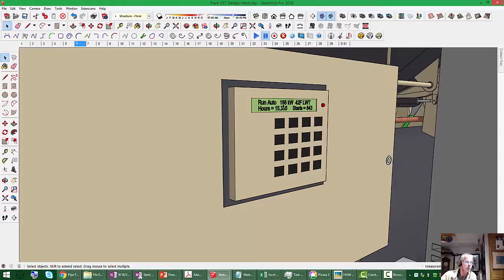And in terms of full capacity, how much is this machine rated for? Well, you could use the pump nameplate information, and you might find a nameplate on the chiller, but interestingly enough, most chillers don't actually have the rated tonnage on them, not on a nameplate. You have to get into the submittals for that. But a field clue would be the flow rate through the evaporator and the flow rate through the condenser. And so, for instance, we know the pump in this evaporator is an 1100 GPM pump.